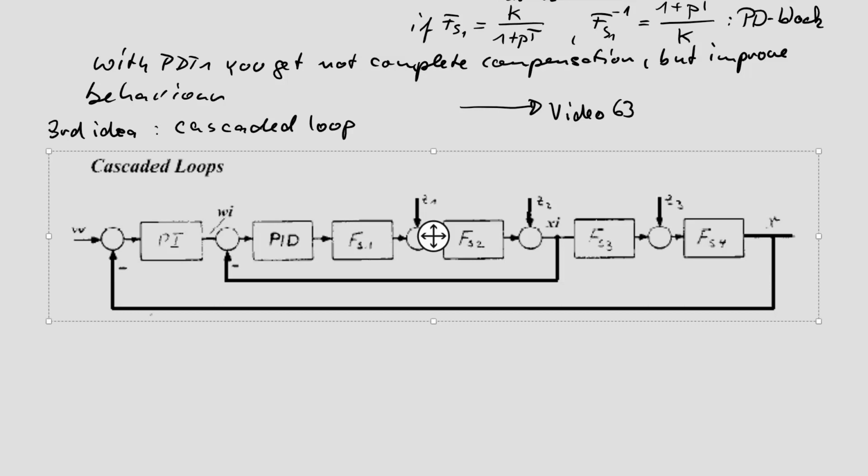And what happens now is that if Z2 is changed, automatically at once xi is changed, and this change is sent to my internal controller. The reaction can come at once with the differentiator very quickly, and the reaction has to go through FS1 and FS2 and then can compensate Z2. So the way to compensate Z2 is much shorter.